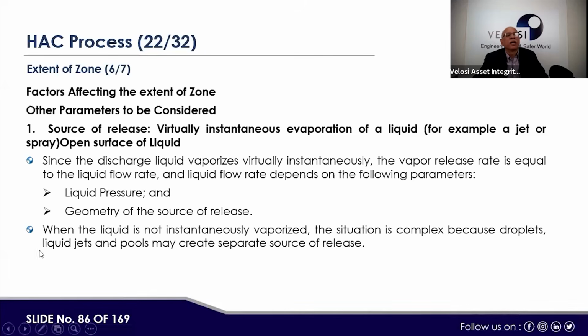Then for a source of release with virtually instantaneous evaporation of the liquid, for example a jet or a spray, since the discharged liquid vaporizes virtually instantaneously, the vapor release rate is equal to the liquid flow rate, and the liquid flow rate depends on the following parameters: liquid pressure and geometry. When the liquid is not instantaneously vaporized, the situation is complex because droplets, liquid jets and the pool may create separate sources of release. So here, we have to look at certain simple examples.